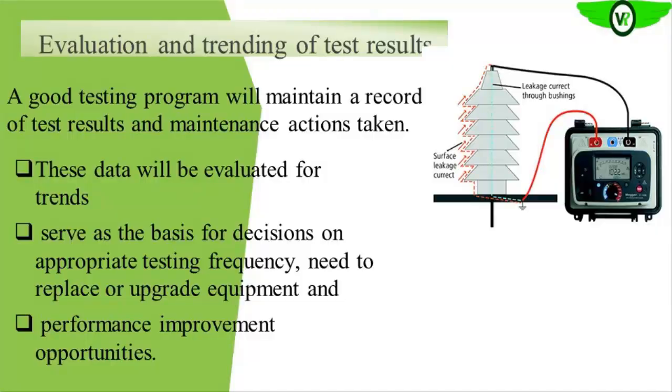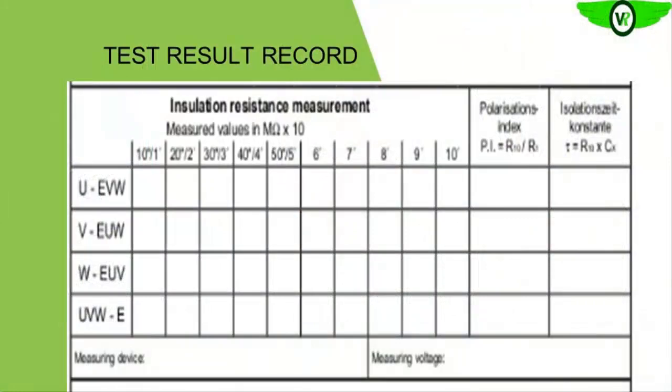A very good maintenance program must have a provision to be recording your test results each time you go out to carry out your test, so that once a trend is developing, you will see it clearly from your records. And if you trend it, that is, you plot it, as deviations are happening, you will see it on the trend results.